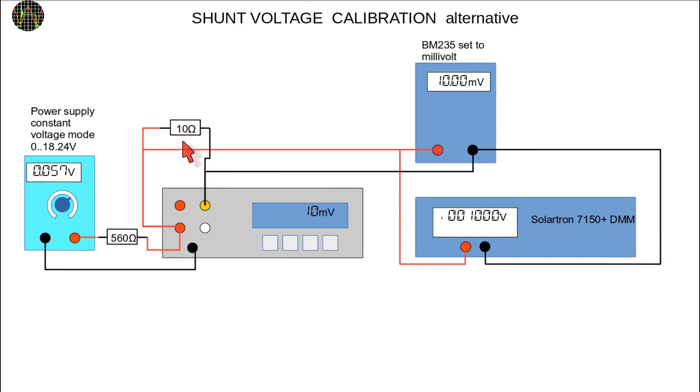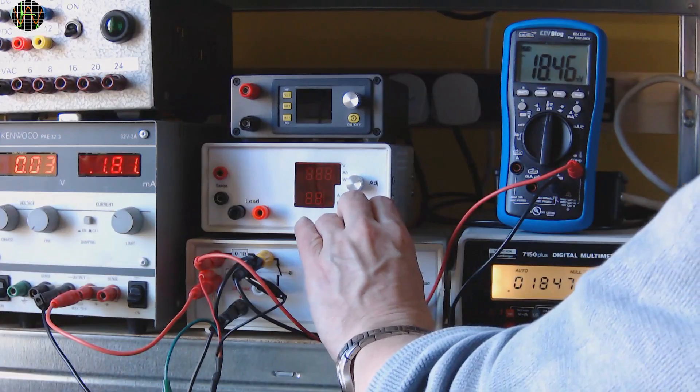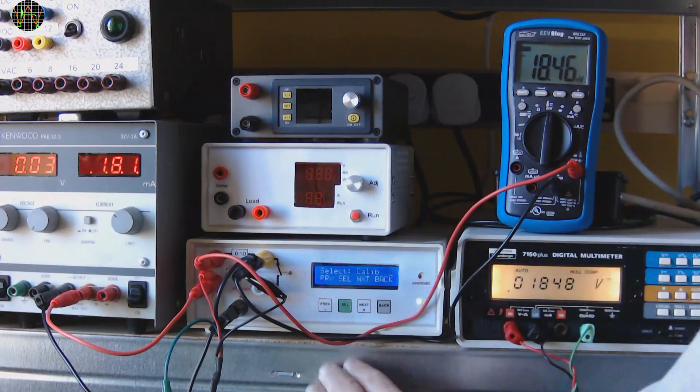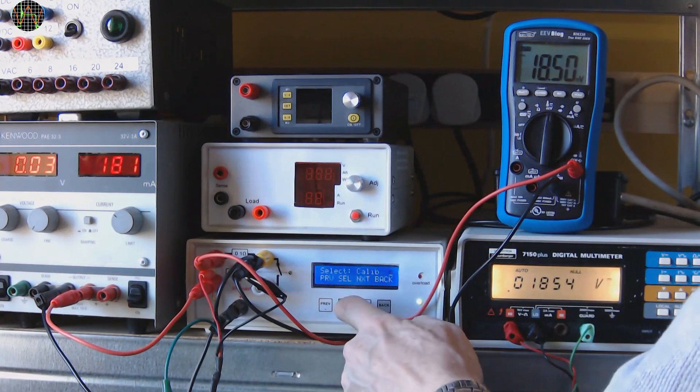We only use it temporarily for this setup and as I explained the shunt voltage calibration is independent of the actual value of the shunt resistor. Selecting the calibration menu and shunt voltage A for the first calibration.